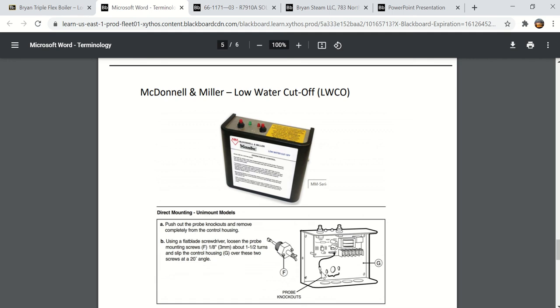You hook up the little eyelet there to the wing nut, and through the electronics here, and here's your terminal strip, it will determine whether or not there is conductivity through the water to the ground point, which is the actual base here. And one of the things that's very important, now that you know that conductivity to ground, you have to make sure that the casing of this box is securely mounted to this brass hex plug here, because if it's not, you're not going to get a good ground reference. So if you take the box off or it's loose on there, that could give you problems.